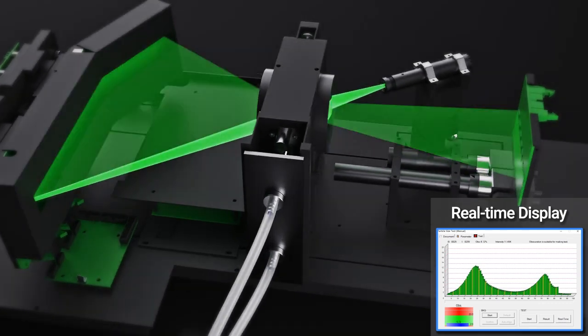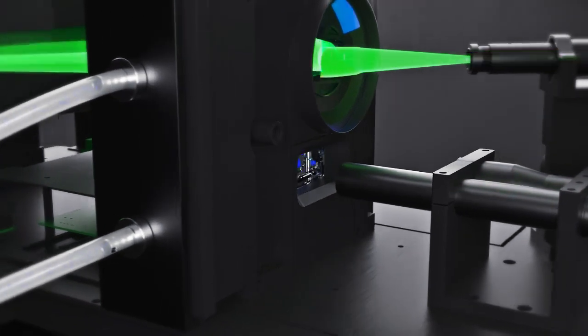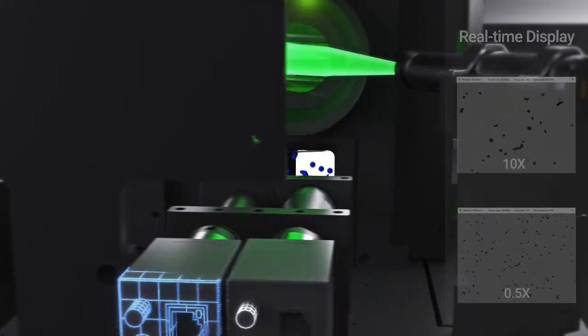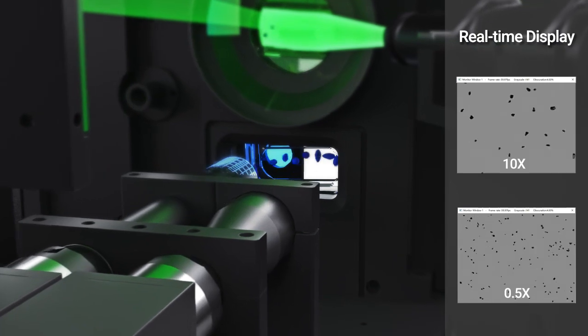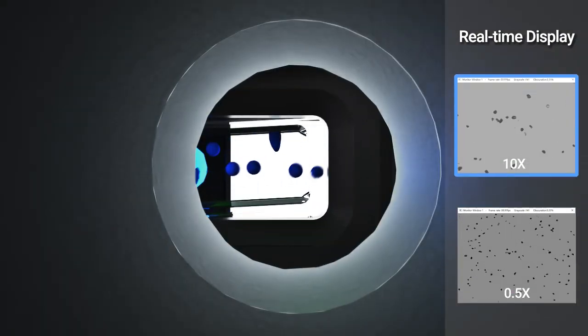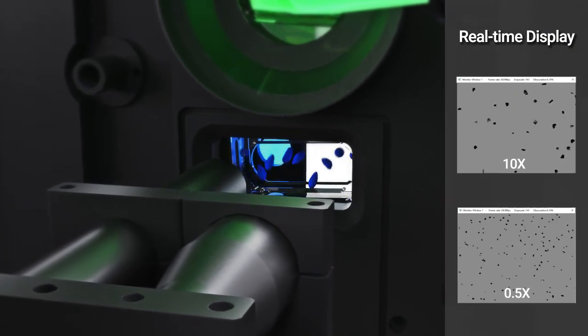Meanwhile, the dynamic image analysis achieves the reliable detection of coarse particles through two high-resolution digital cameras, 0.5 times and 10 times, thus raising the upper limit of measurements to 3.5 millimeters.